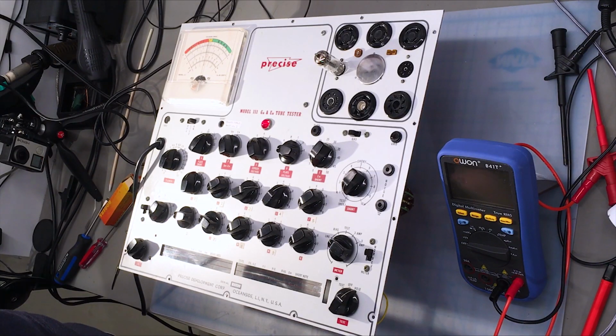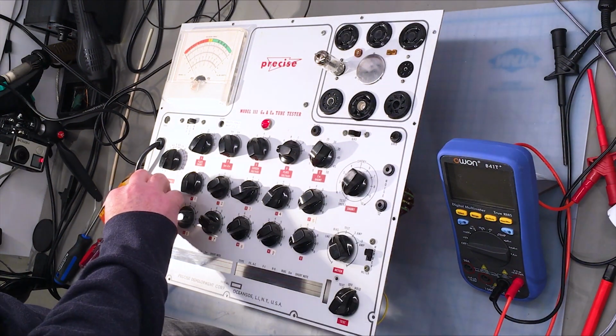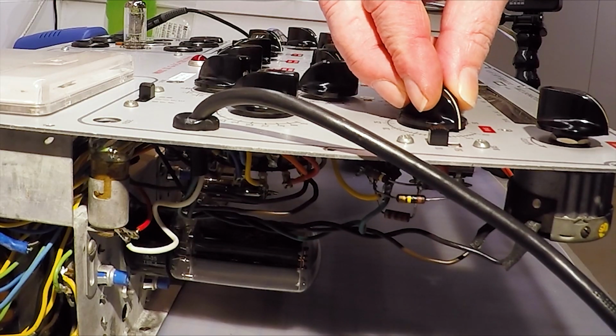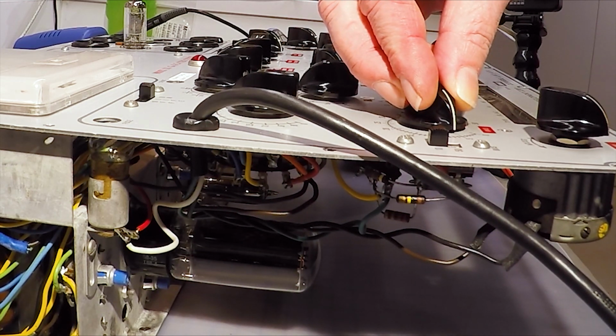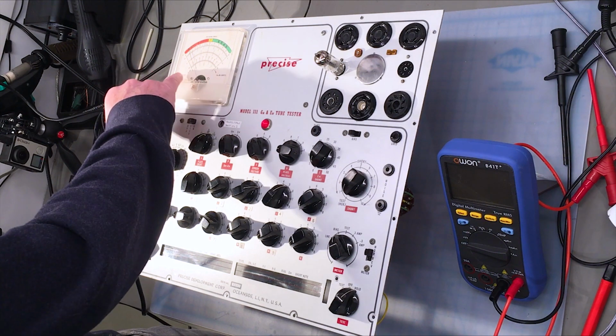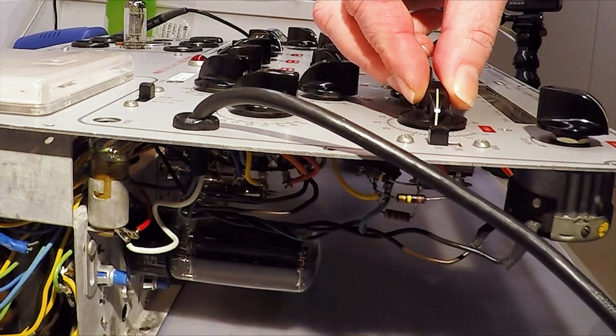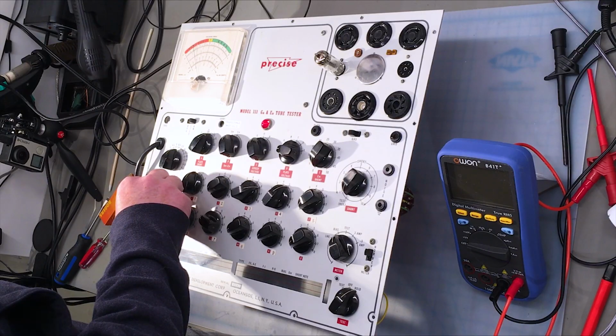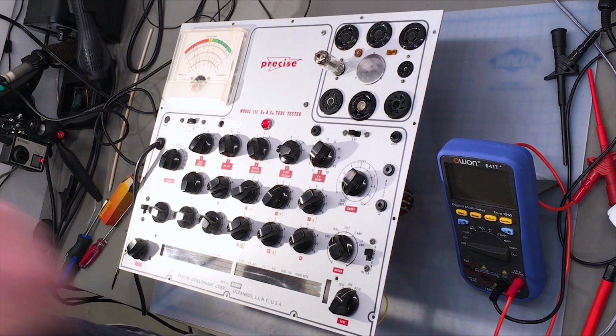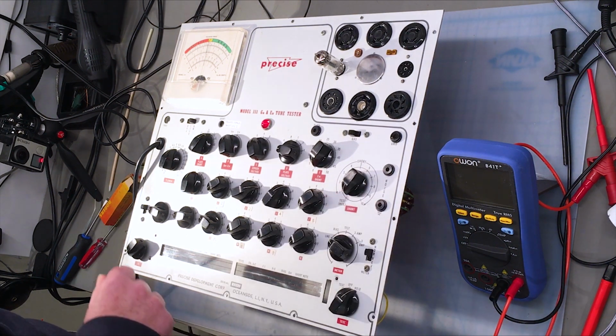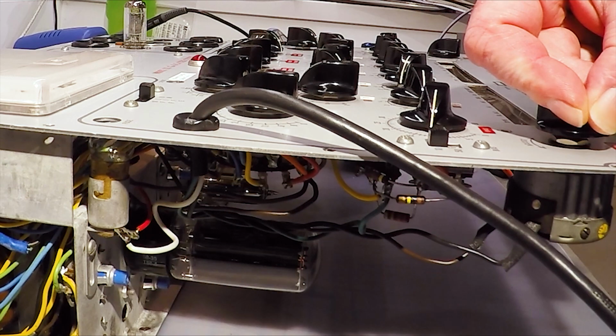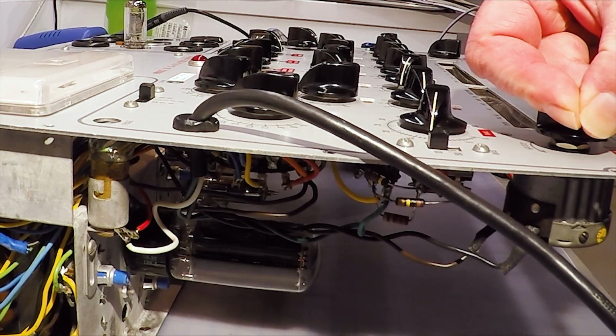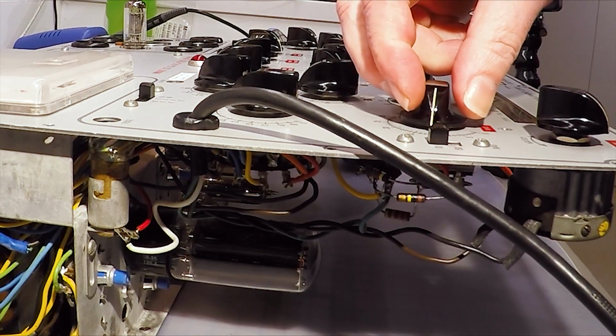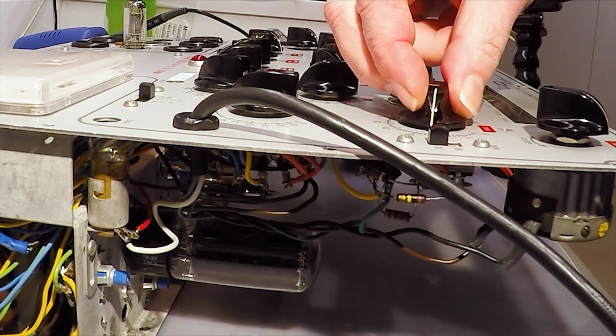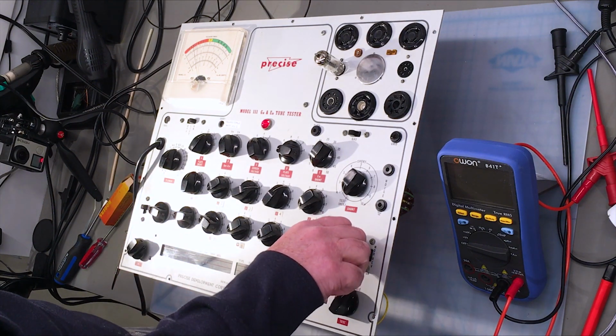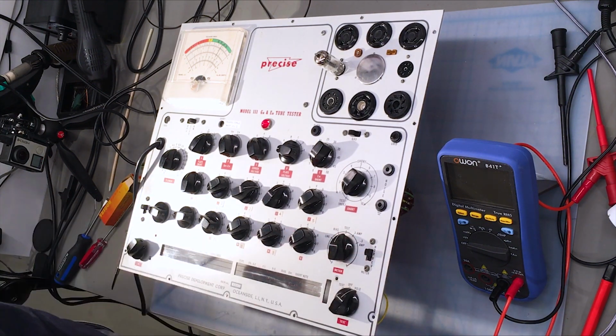Then we rotate the meter switch to bias, and we rotate the bias control such that we have 10 volts on the bias voltage reading. And this is the bias voltage on this portion of the meter. And we're looking for 10 volts of bias voltage. And that's 10 volts right there. Now we're to repeat C and D, because there's the possibility that by adjusting the bias voltage, we've affected the line voltage setting slightly. And again, we go to bias voltage adjust and make sure we're at 10 right on the button. There we are.